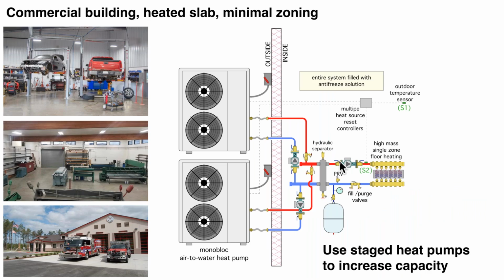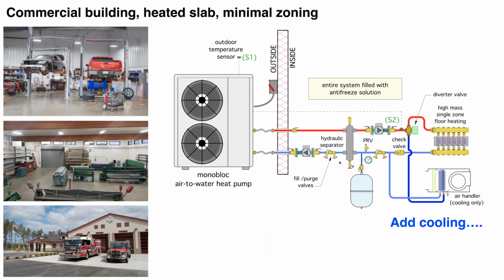Real quickly, I expanded it to 2 heat pumps here in a commercial facility. If you have single phase power, you might need 2 based on heating capacity. And then finally, if they're doing the air to water heat pump primarily for heating, why not add cooling into the mix? It could be as simple as 2 manual valves that you change to change the distribution side from heating to cooling or vice versa, or some type of electrically operated diverter valve, but a suspended air handler with minimal ducting.